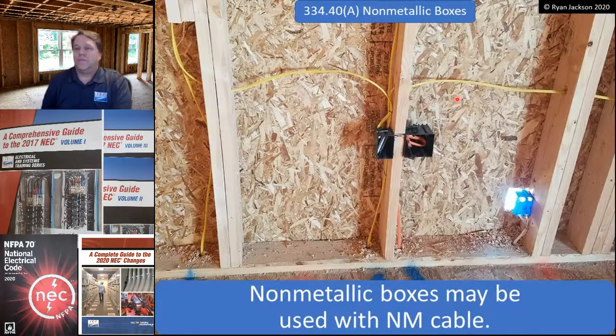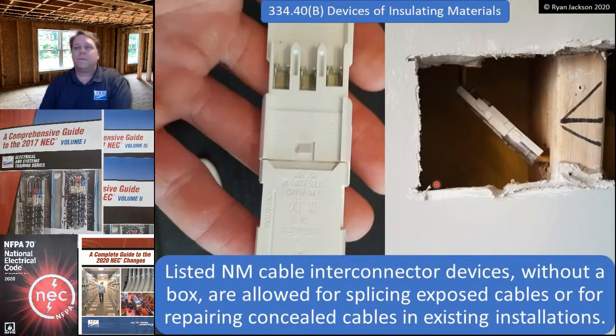334.40, boxes and fittings. Non-metallic boxes may be used with non-metallic cable. Yeah, you can use plastic boxes with your plastic wiring. Not a problem. Devices of insulating material. See, I keep on dropping those frames. Let me just make one more change here. I'm going to drop this down on the bitrate. Listed NM cable interconnector devices without a box are allowed for splicing exposed cables or for repairing concealed cables in existing locations. Okay, so this is the fitting that we're talking about, and I actually have one of these little guys here in my hand. This allows me to make a splice of NM cable and then bury the splice behind the wall.